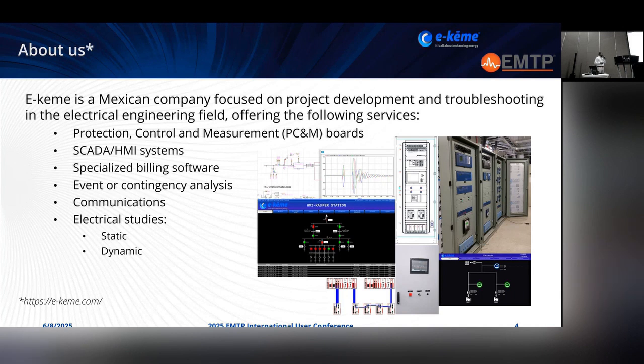Finally, our work spans through the electrical studies, and in this part we normally do static type of simulations, like protection coordination, short circuit, harmonic, load flow, and well, this spans also to dynamic type of simulations, delivering mathematical models to CENACE, who's Mexico's grid operator, and also PPC tuning and some transient stability analysis.